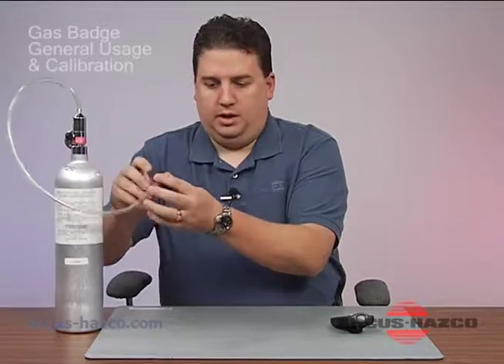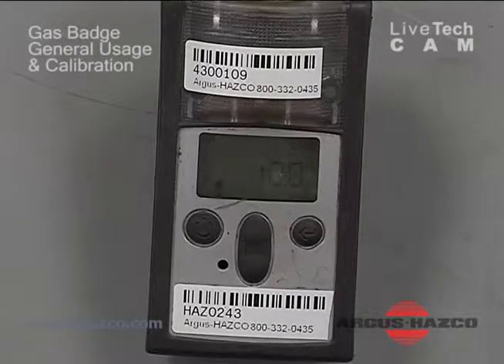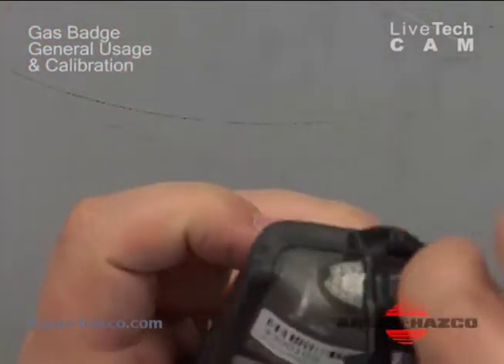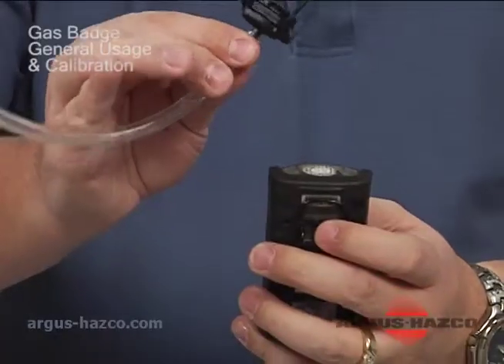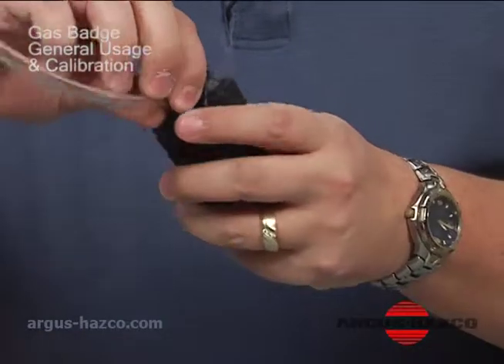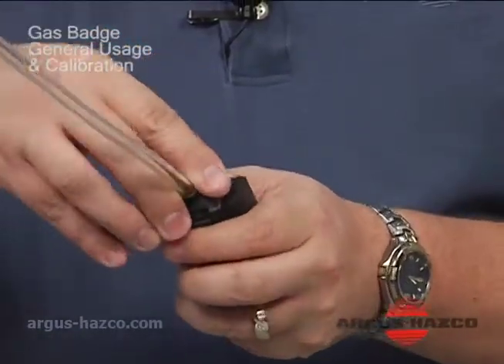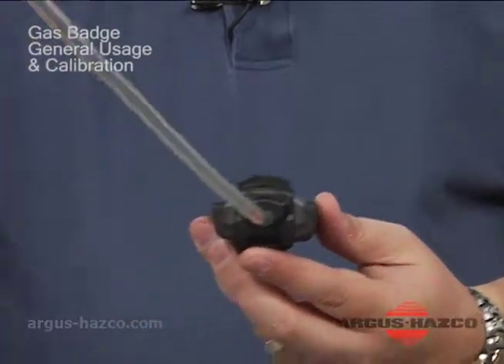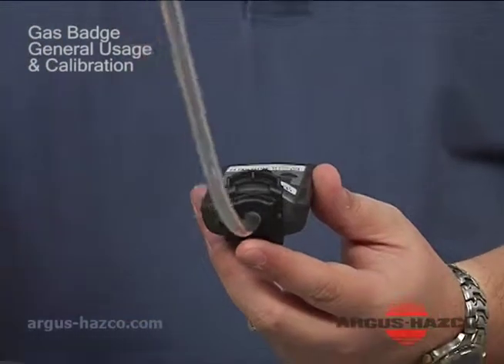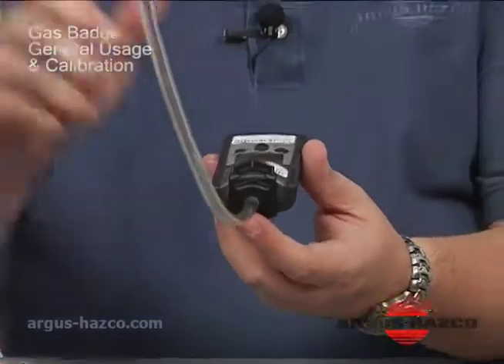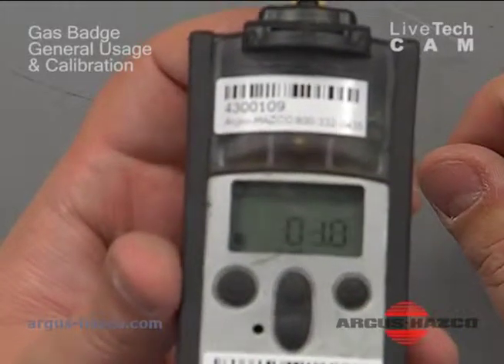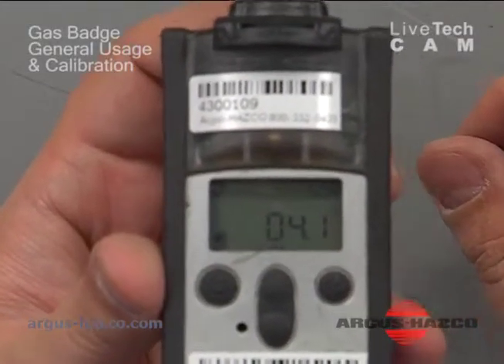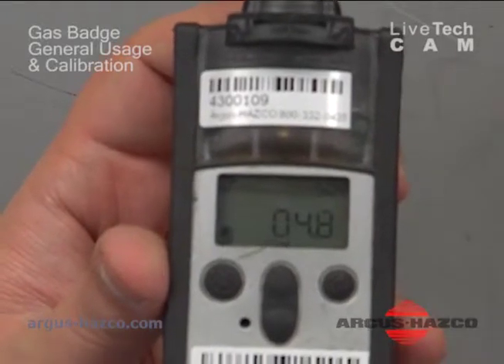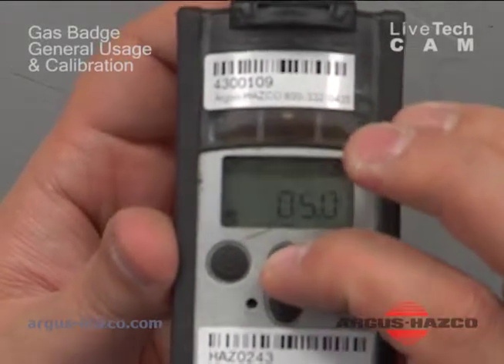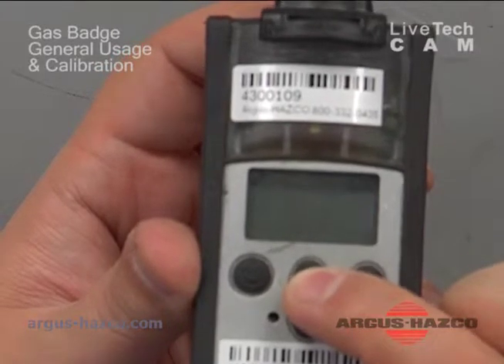So I'm going to put on my cal adapter onto the instrument. At the top here, you'll see the cal adapter snaps on. And I'm going to turn on the gas. At this point, you can tell it's already timed out. You have 30 seconds basically to acknowledge a function, or it's going to time out and go back to the normal screen.